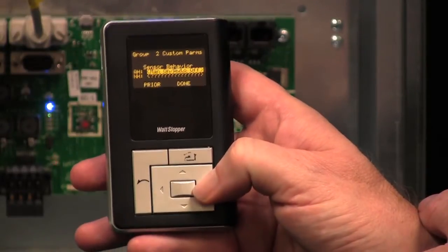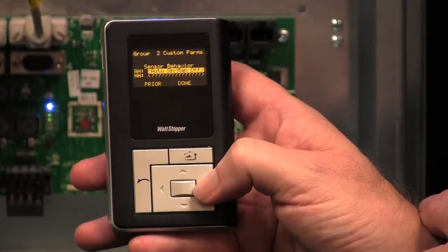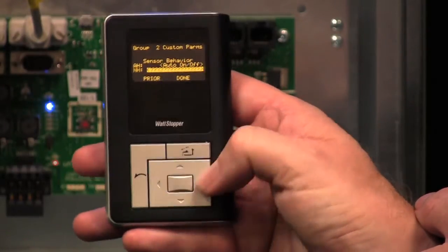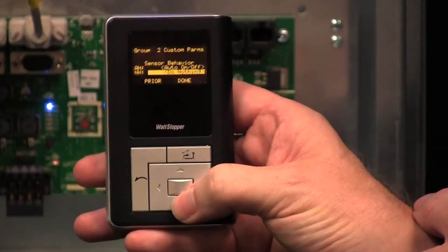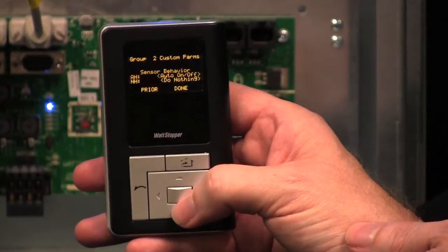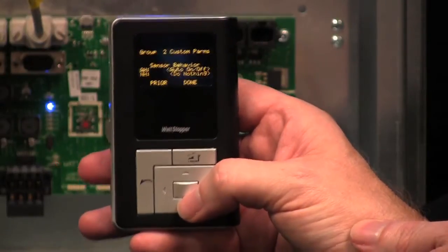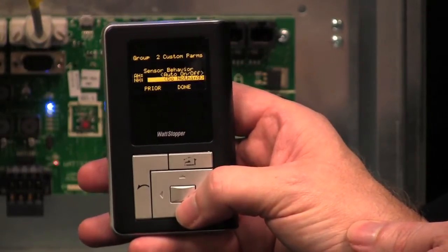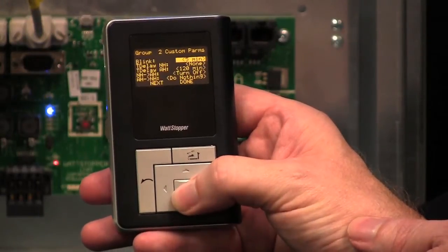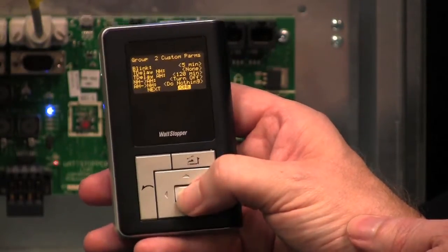After hours, I'm going to want the sensor to go automatic on and automatic off. But during the normal hours, I don't want the sensors to do anything. So now I can have my lights go on in the morning by a schedule, and after hours, I can hand control completely over to the occupancy sensors. Since I'm done with this little menu, I'm going to say done, done.